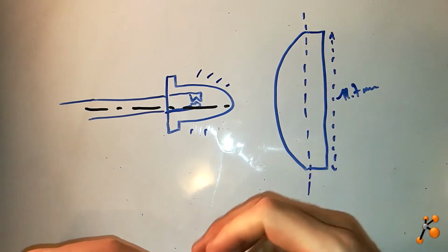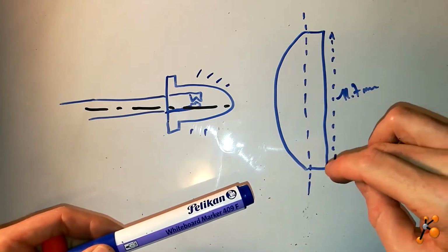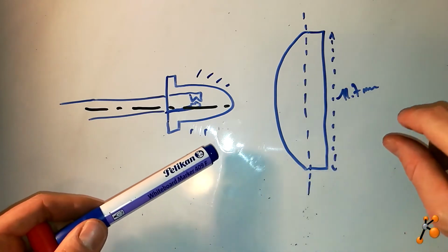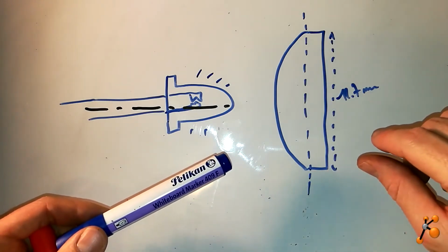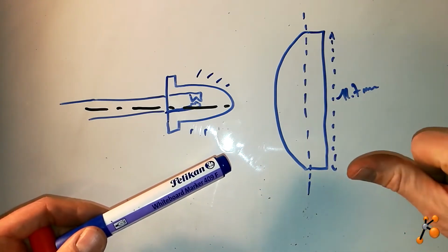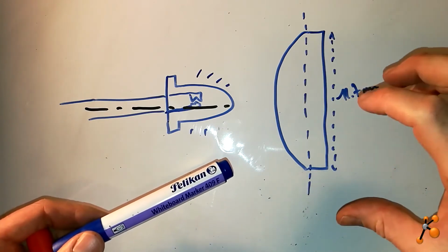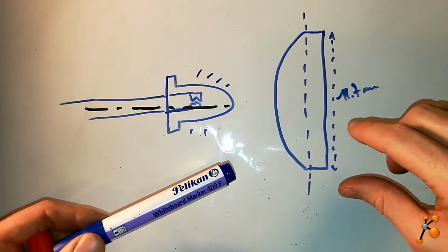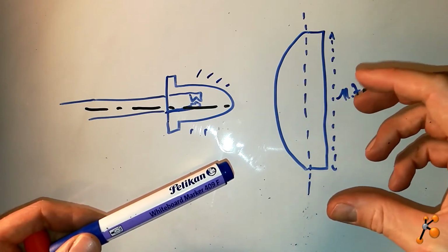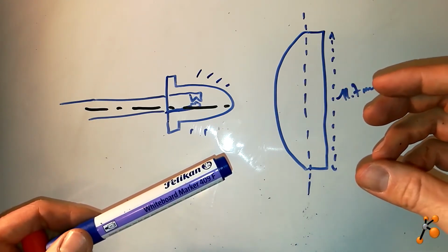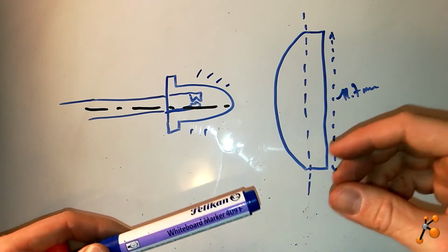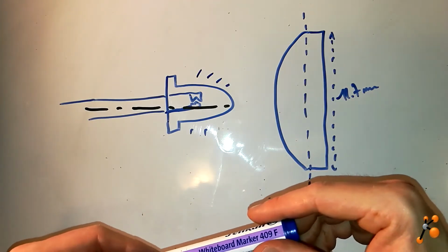So the lens, you have to be careful when you buy it. Sometimes they can have a coating, and this coating is very thin, like a nanometer, and they are really sensitive to temperature, they can crack, and they're also sensitive to the air pressure, and also you should not touch without glove, so you have to use latex-free glove.